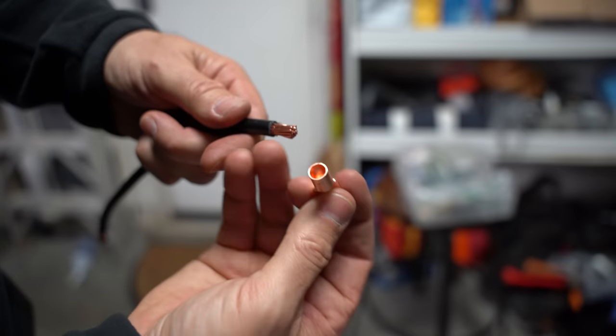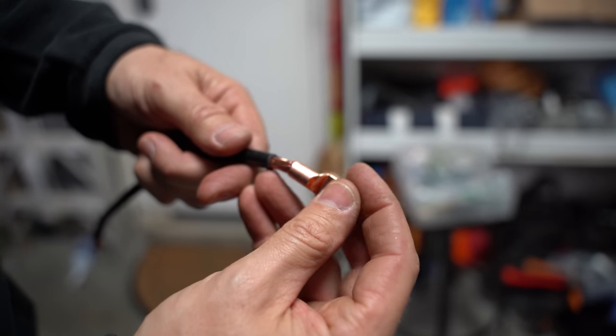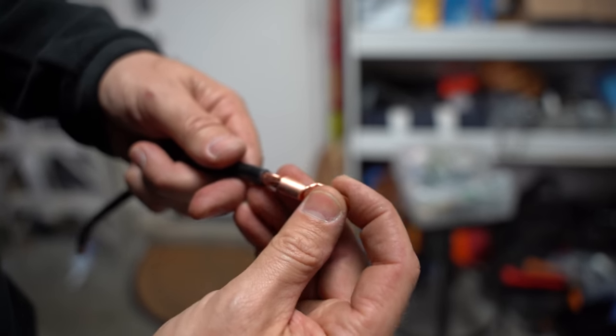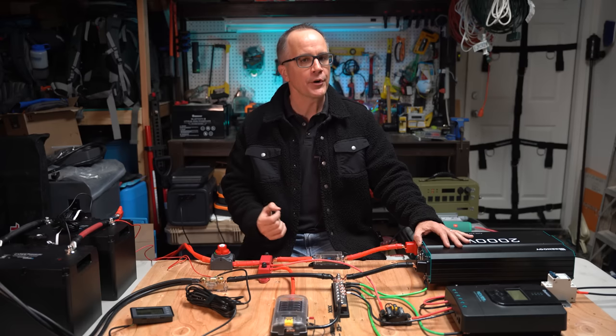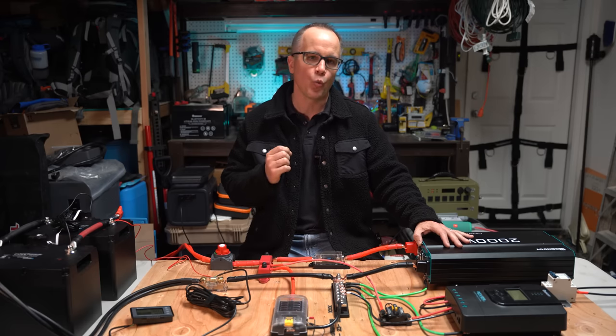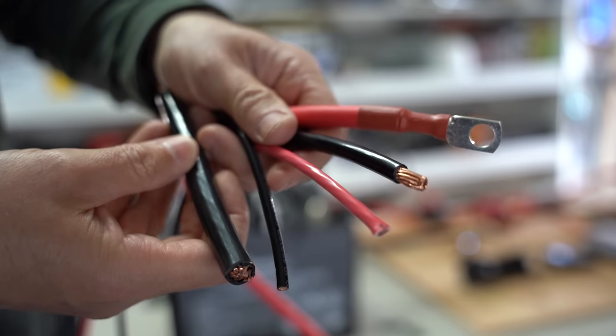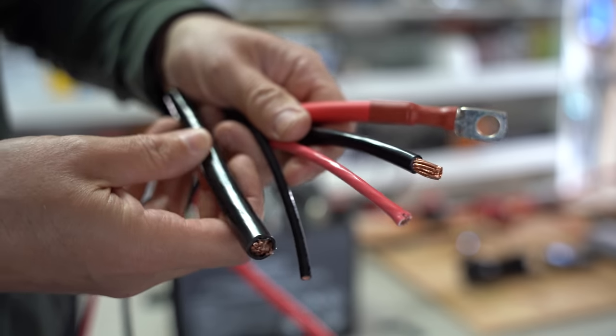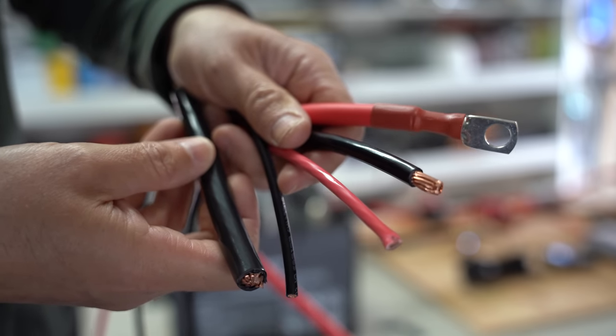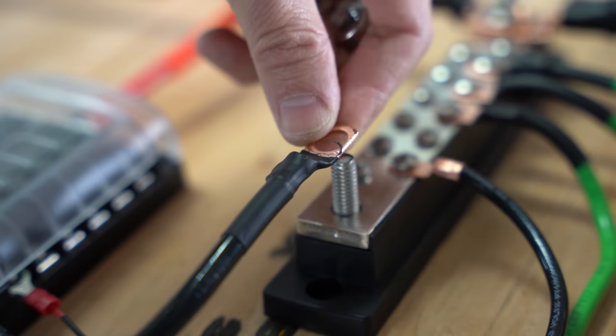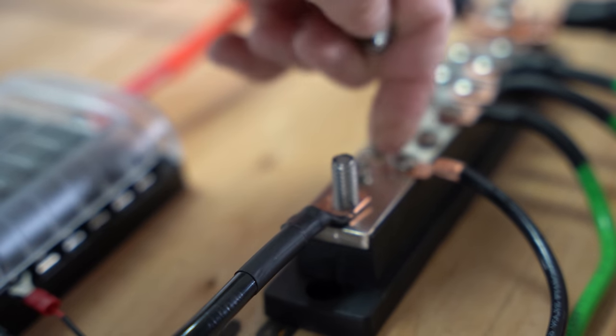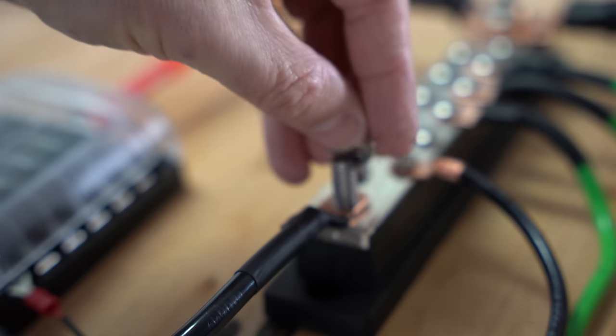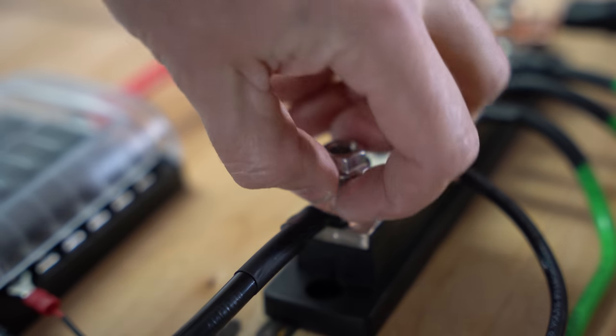There are a few things that you'll need to pay attention to. The first is the wire gauge size you can put this on. Remember in our previous point that we discussed the size of the wiring that we're going to be using. Once we start building this setup, we're going to see that we'll need different wire sizes for different devices in our system. Next, we need to pay attention to the size of the inner diameter of the screw or post that we're going to be connecting this lug to.